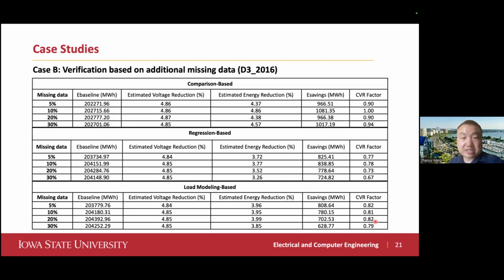This case B is on D3, with 5% to 30% missing data. You can see how the CVR factor is calculated. Again, for this data set it's fairly consistent, giving us confidence that the CVR factor should be around 0.8 to 0.9 for this feeder. So what's the conclusion for this part of the study?